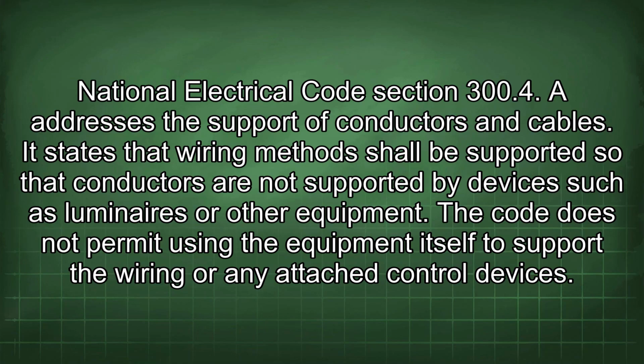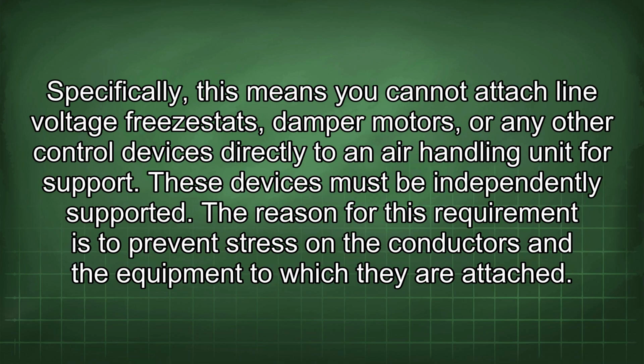National Electrical Code Section 300.4 addresses the support of conductors and cables. It states that wiring methods shall be supported so that conductors are not supported by devices such as luminaires or other equipment. The code does not permit using the equipment itself to support the wiring or any attached control devices. Specifically, this means you cannot attach line voltage freezestats, damper motors, or any other control devices directly to an air handling unit for support. These devices must be independently supported.